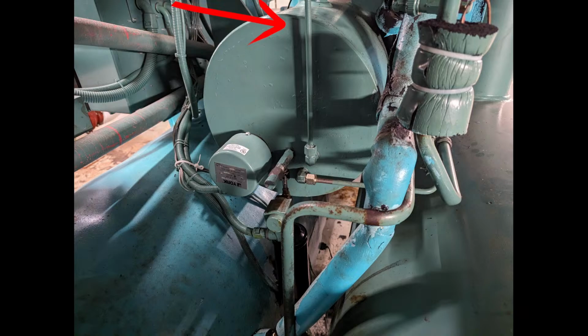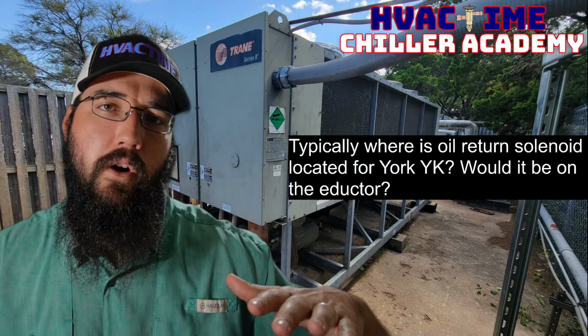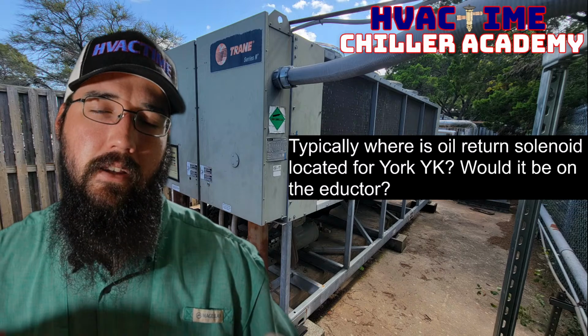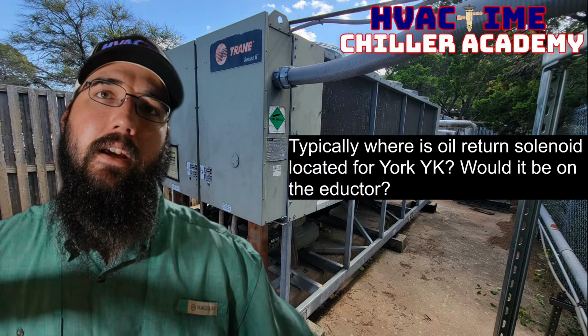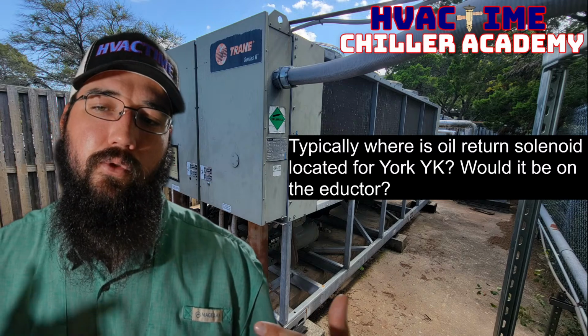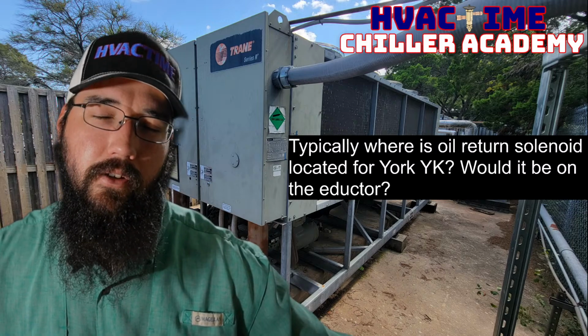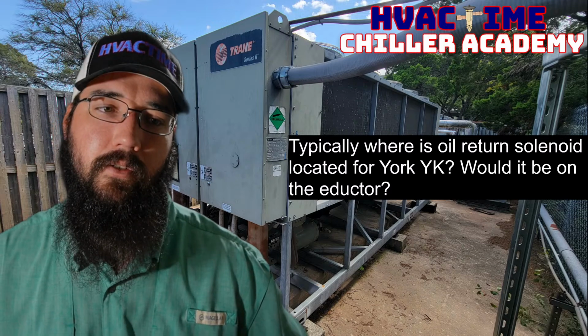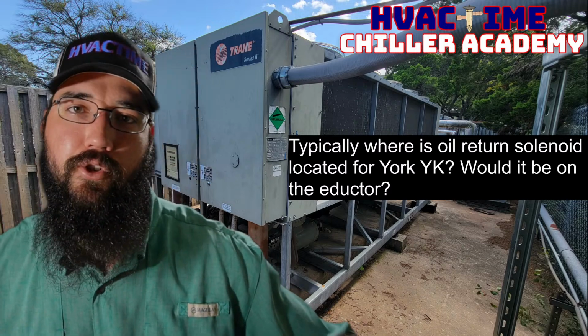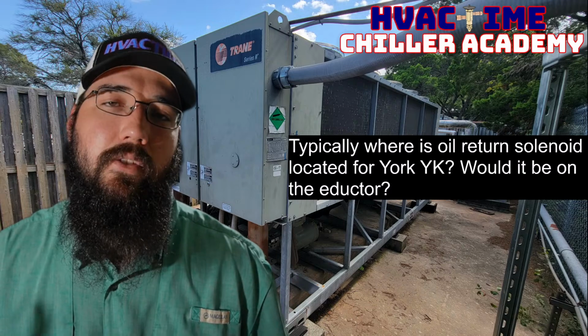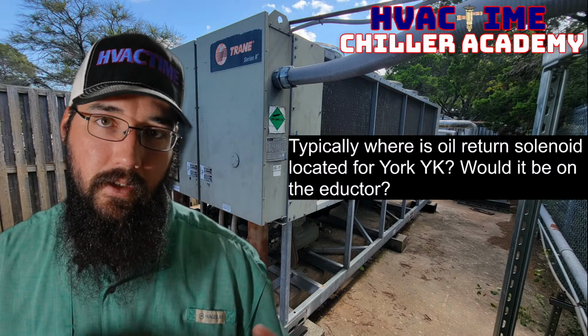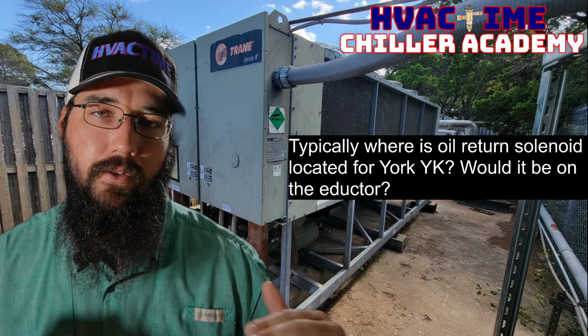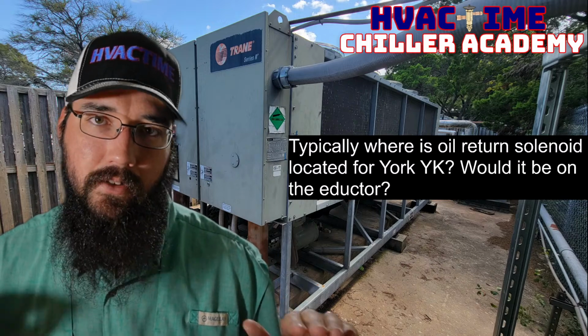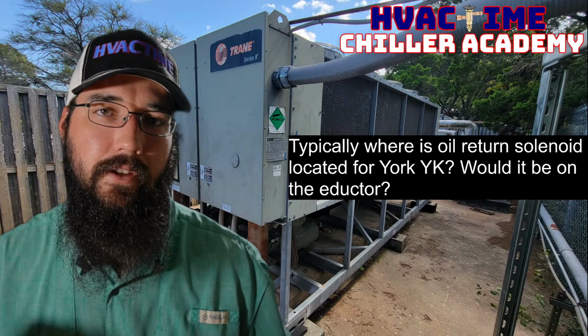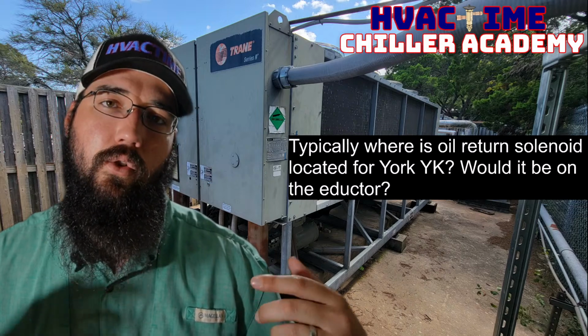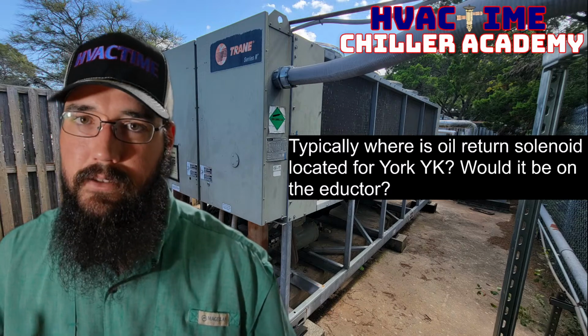We have to be very careful in where we're maintaining that liquid level in those machines, so that when we are using that solenoid valve to control the eductor oil recovery system, we're not undershooting or overshooting. And there is this little sweet spot, which York specifies that they want to see right about half glass. In a perfect world, their evaporator, when everything is balanced and tuned correctly, is going to run about half glass in that sight glass, so you should be targeting about that region.